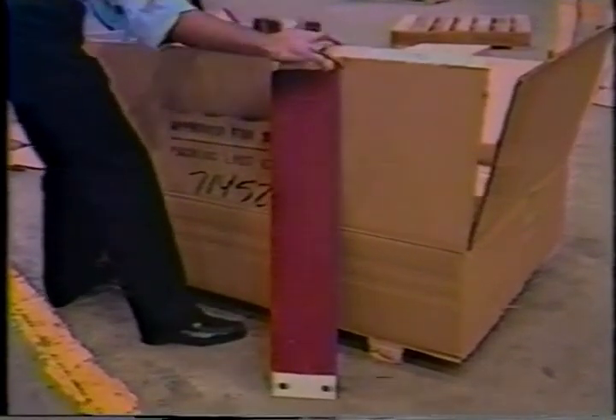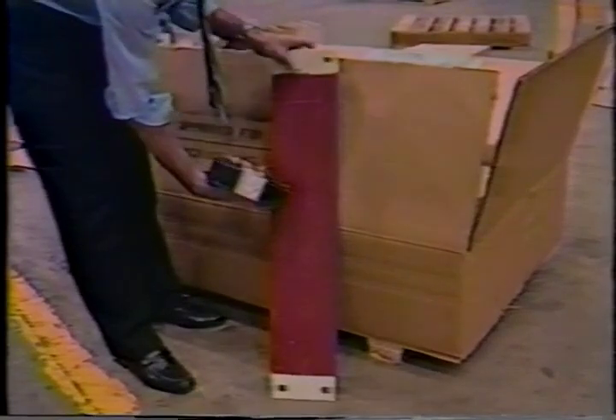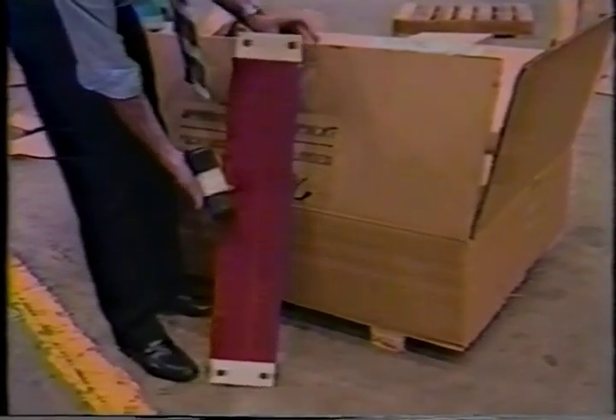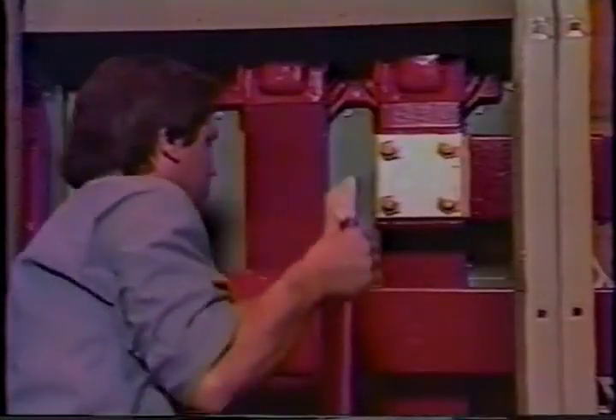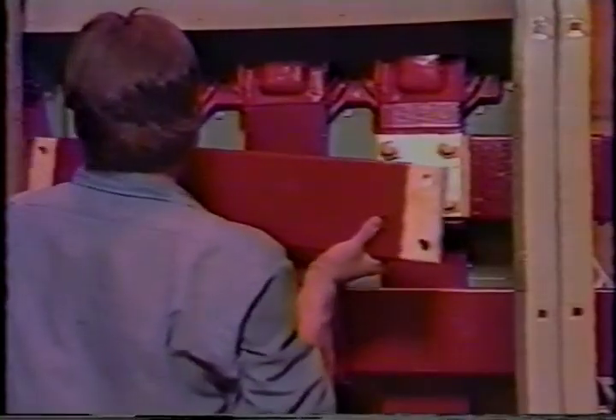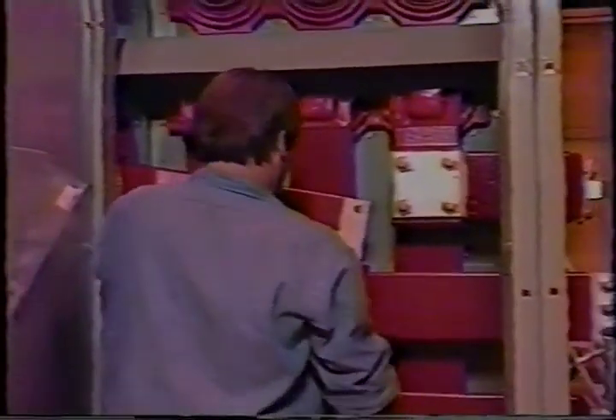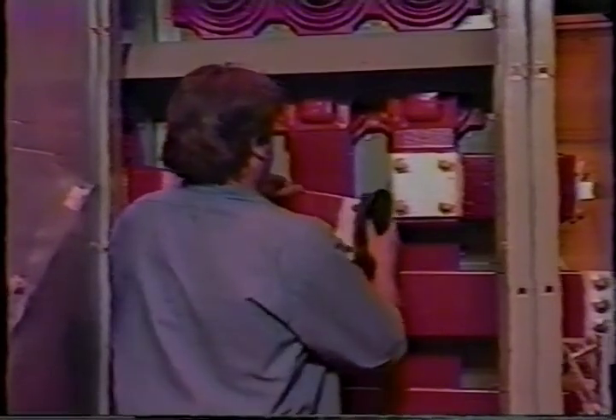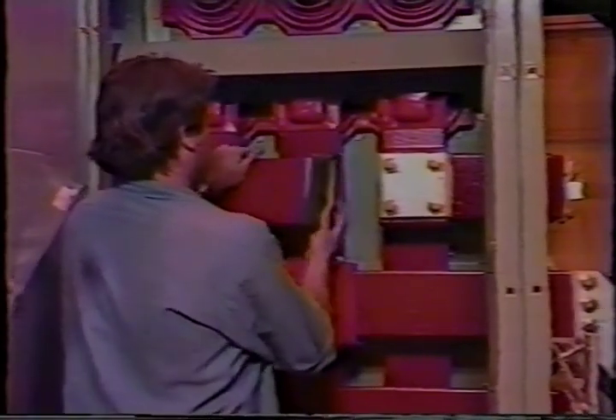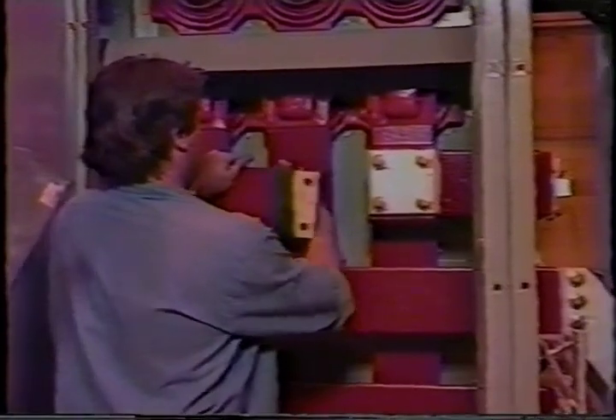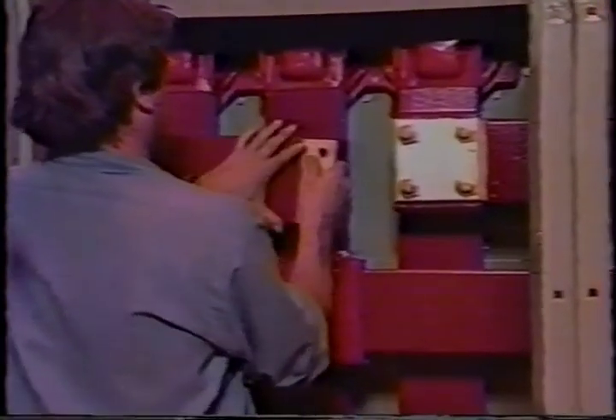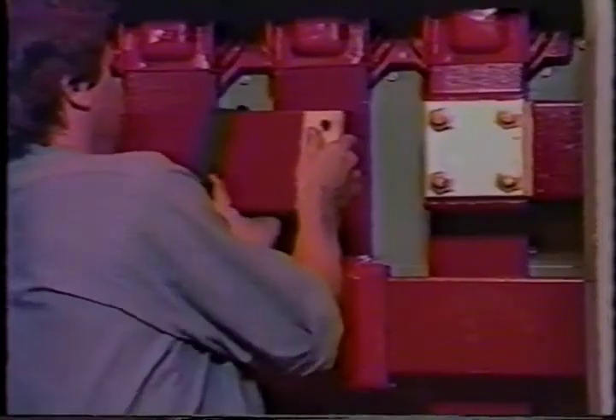Obtain the bus sections and black rubber snubbers to bridge the split. These will be found packaged with the switchgear accessories in the cardboard detail box. The plated surfaces of the bus should be cleaned if necessary. Slide the section of bus through the supports in the side of the vertical section. Slide the rubber snubber along the bus until it fits inside the opening in the bus support.